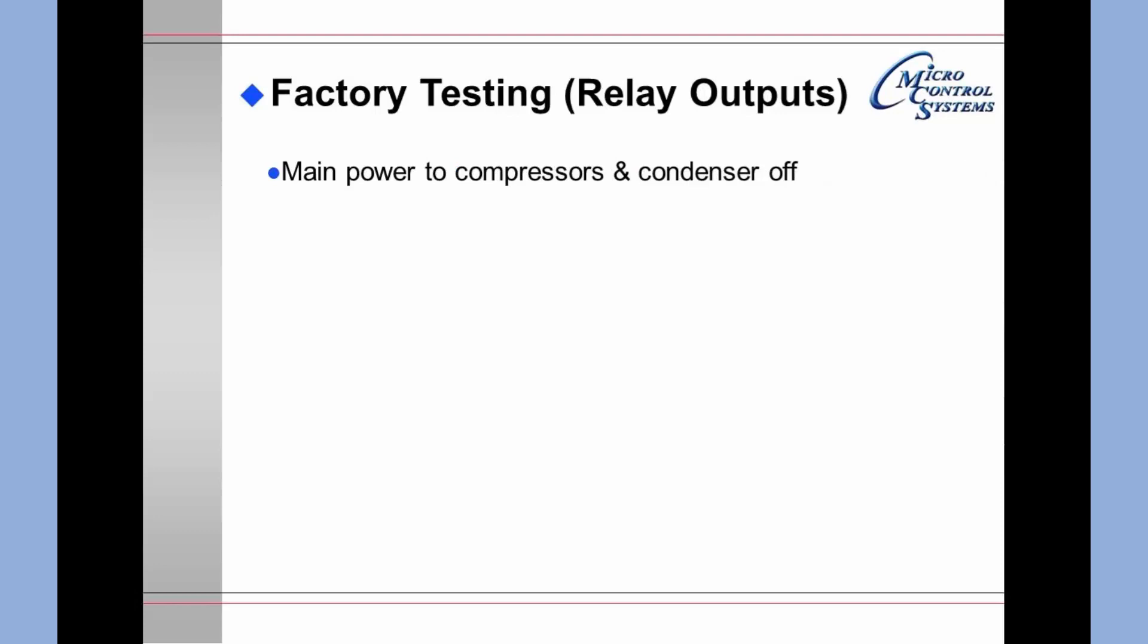During the factory testing on the relay outputs, the main power to the compressors and the condenser should be turned off. Control power to the micro and the contactors and the solenoids should be on. You may need to put together a separate extension cord type system in order to do this.